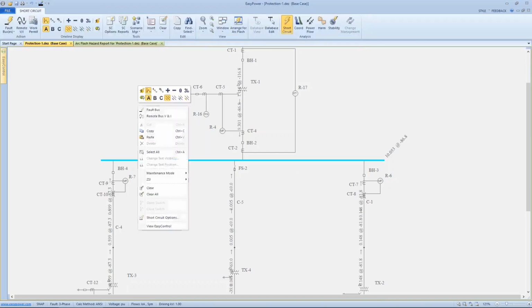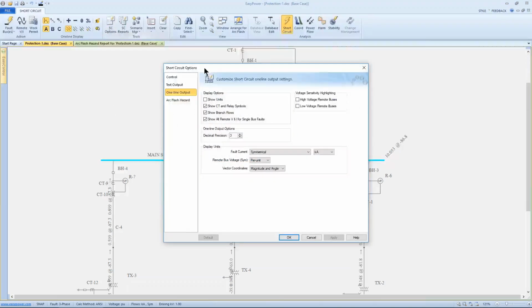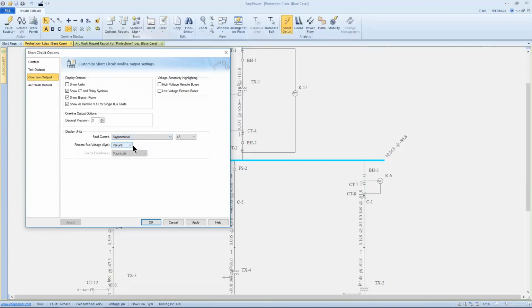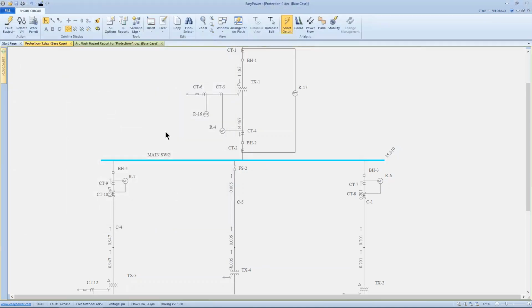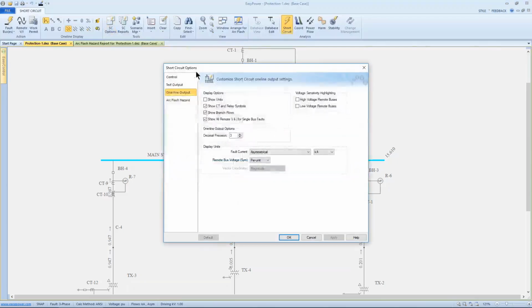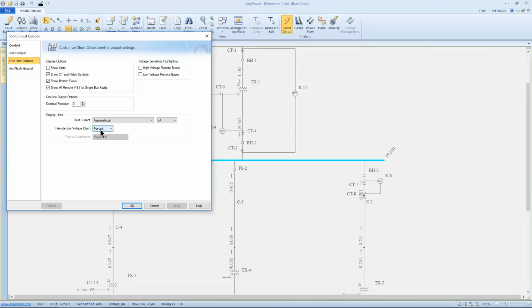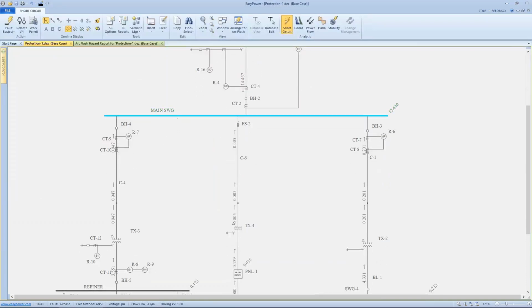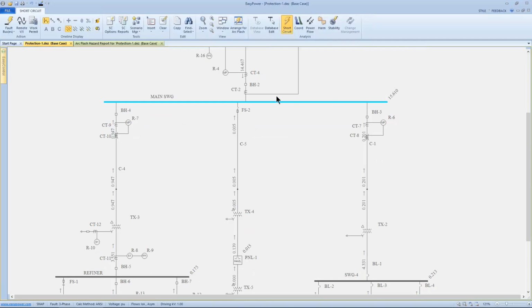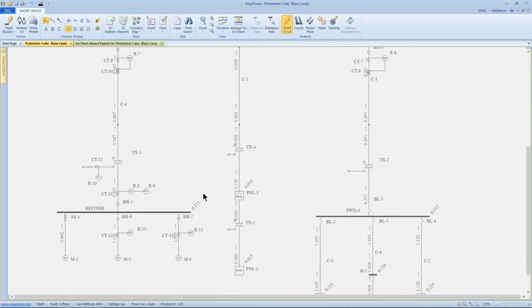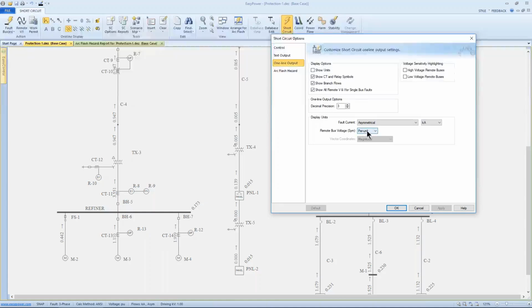Now, if we come back to our short circuit options, if we want to look at asymmetric, we can do the same by selecting the display to be in asymmetric terms. And again, we're showing only the asymmetric magnitude. On the remote bus voltage, we're seeing per unit values, and this is for a single bus fault. If we fault just this one bus, then this gives us our total current. We see the total magnitude, again showing asymmetric. On a remote bus, we're showing the branch currents, but here we're showing the per unit value of the voltage itself. And if I come back to my short circuit options, that per unit value can be shown in kilovolts on the remote bus.